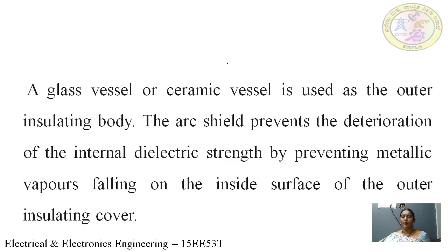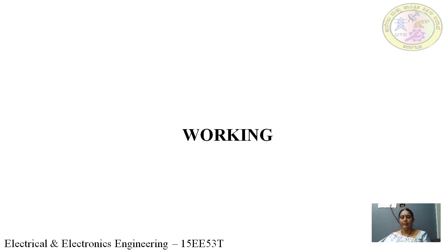insulating body. The arc shield present inside this insulating body prevents the deterioration of the internal dielectric strength by preventing metallic vapors from falling on the inside surface of the outer insulating cover.